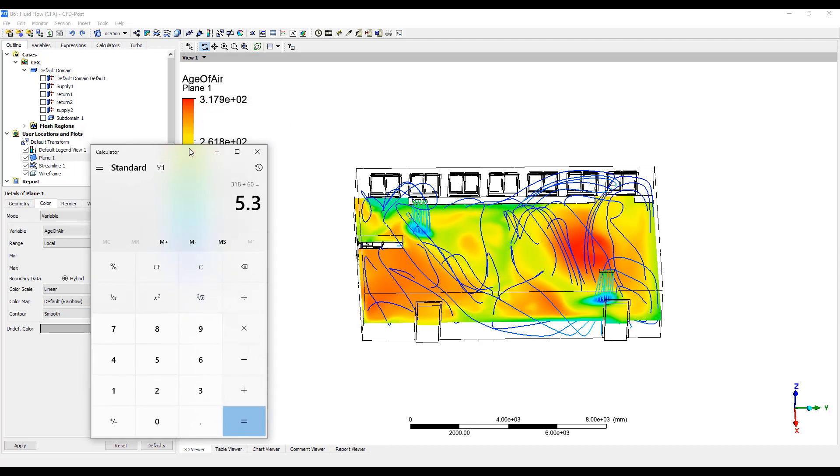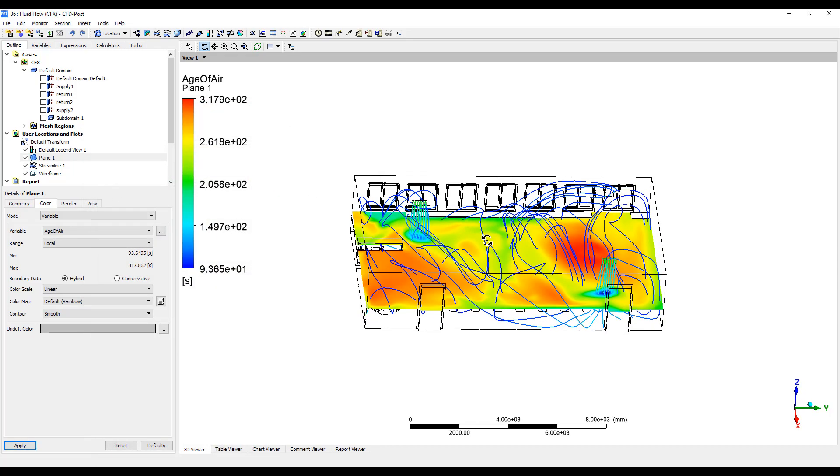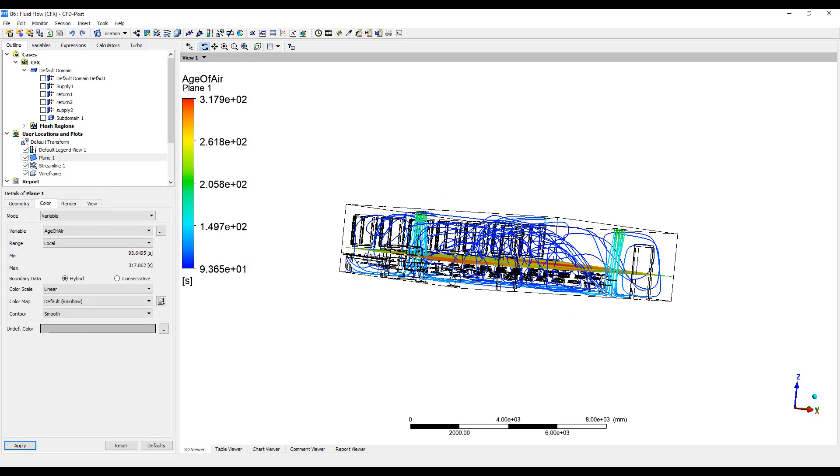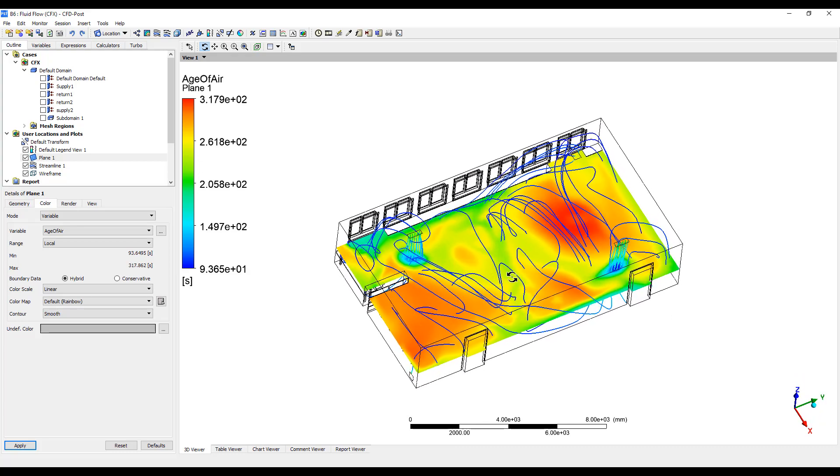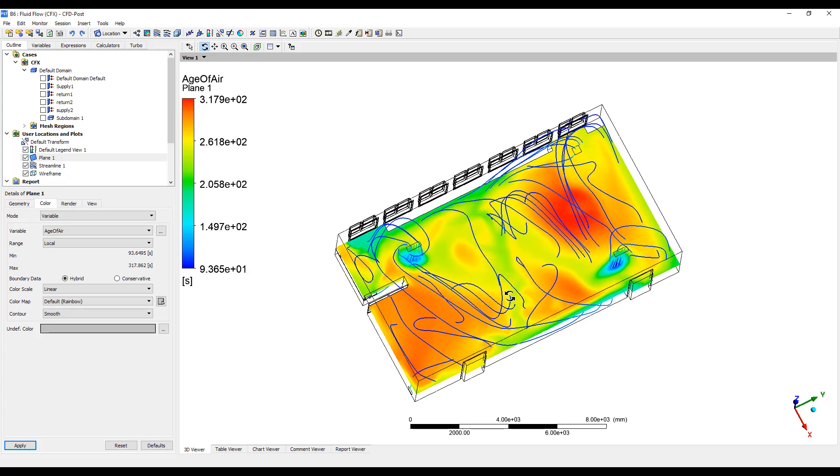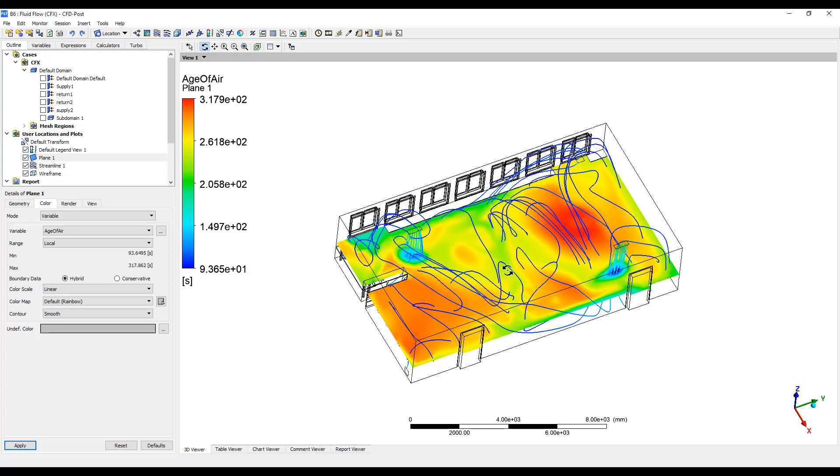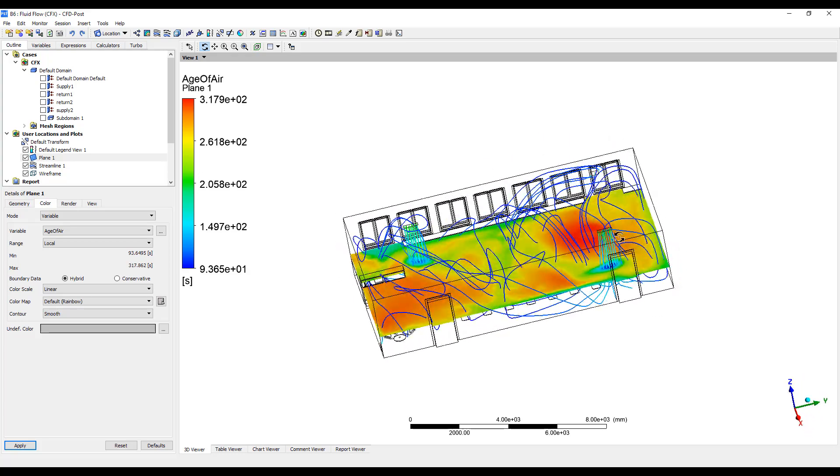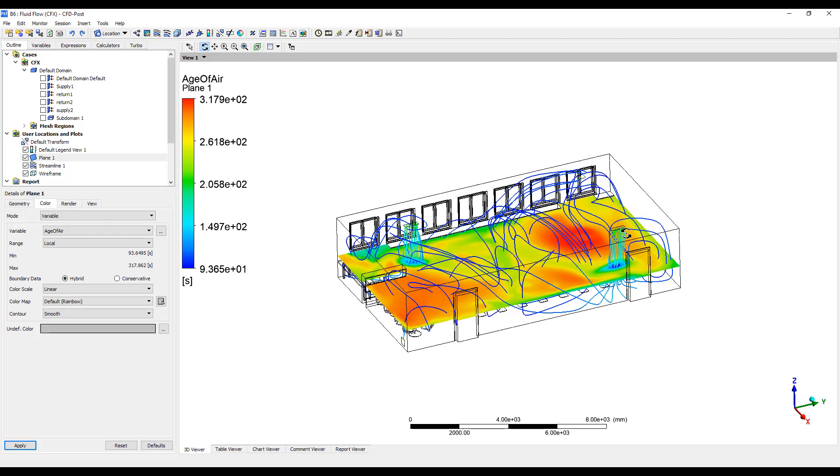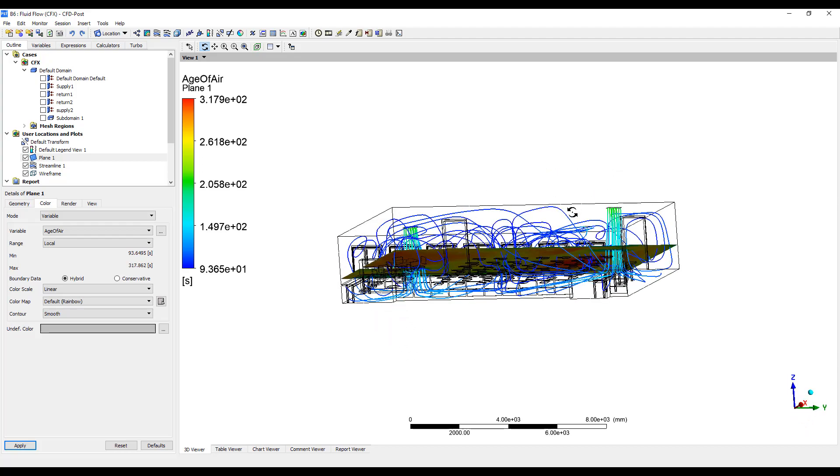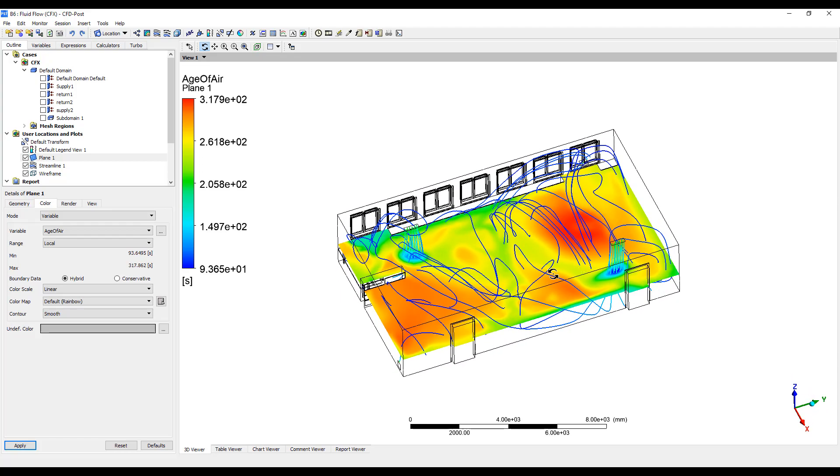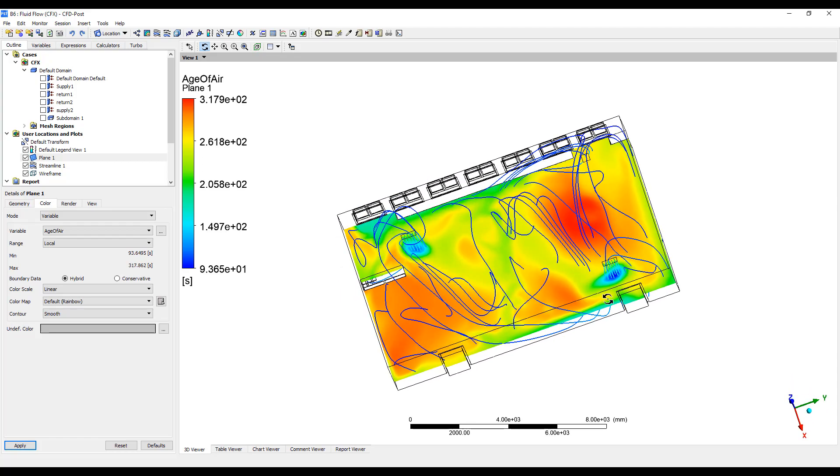So the maximum air has been in that location for 300 seconds, about 5 minutes, which is pretty good. It shows that in this case we have pretty good circulation of air. The maximum amount of time the air has been in this space is about 3 minutes. In certain areas it's much less.